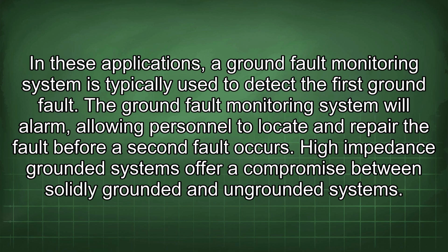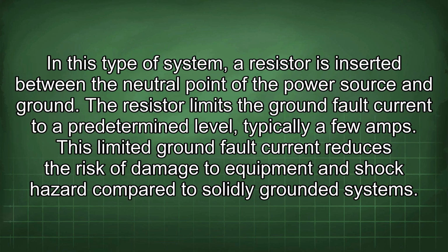High impedance grounded systems offer a compromise between solidly grounded and ungrounded systems. In this type of system, a resistor is inserted between the neutral point of the power source and ground. The resistor limits the ground fault current to a predetermined level, typically a few amps. This limited ground fault current reduces the risk of damage to equipment and shock hazard compared to solidly grounded systems.